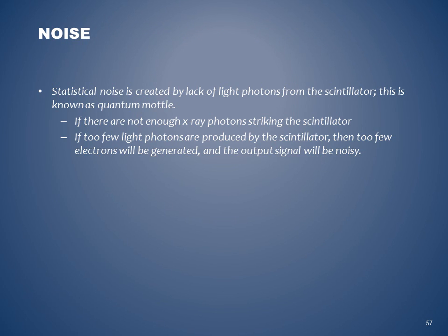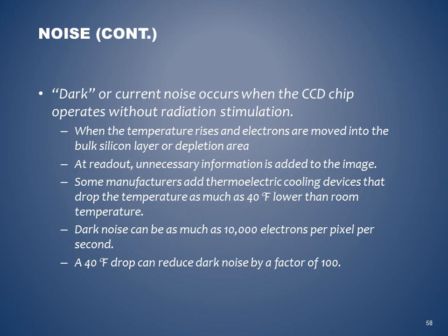Noise. Statistical noise is created by lack of light photons from the scintillator. This is known as quantum mottle. If there are not enough X-ray photons striking the scintillator, and too few light photons are produced by the scintillator, then too few electrons will be generated and the output signal will be noisy. Dark or current noise occurs when the CCD chip operates without radiation stimulation. When the temperature rises and electrons are moved into the bulk silicon layer or depletion area, at readout unnecessary information is added to the image.